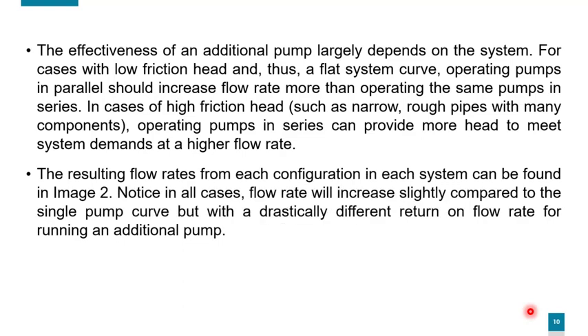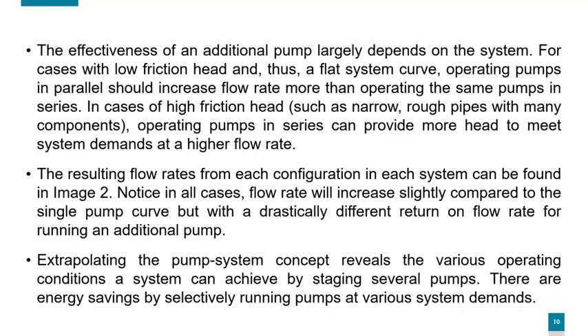The resulting flow rate from each configuration in each system can be found in the previous image, which we've seen before in this video, and we elaborated it for steep and flat systems. Notice in all cases, flow rate will increase slightly compared to the single pump curve, but with a drastically different return on flow rate for running an additional pump. Extrapolating the pump system concept reveals the various operating conditions a system can achieve by staging several pumps. There are energy savings by selectively running pumps at various system demands.